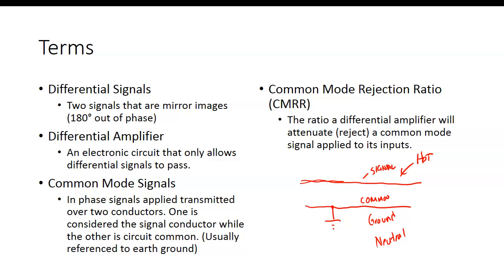So what's the difference between the neutral and the ground? The neutral still sends current back, and the ground sends nothing. In National Electrical Code, they don't actually use the terms neutral and hot. They call this one the ungrounded current carrying conductor, and this one they call the grounded current carrying conductor, or the neutral.